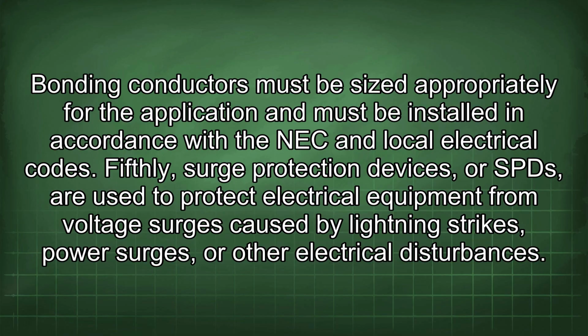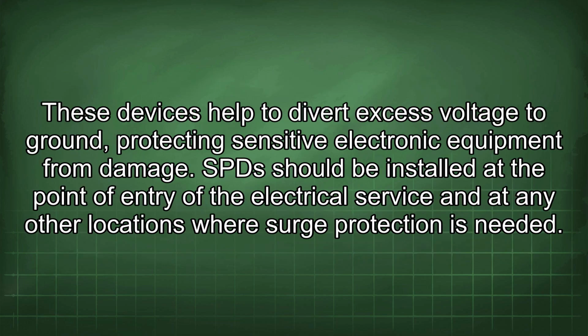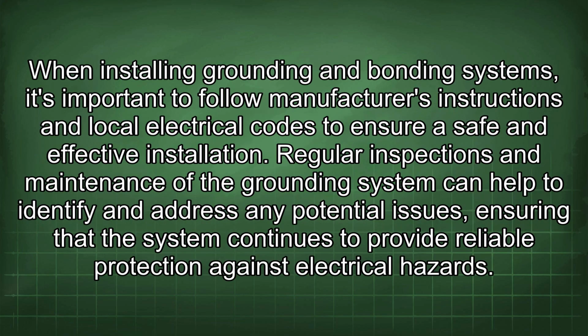electrical codes. Fifthly, surge protection devices, or SPDs, are used to protect electrical equipment from voltage surges caused by lightning strikes, power surges, or other electrical disturbances. These devices help to divert excess voltage to ground, protecting sensitive electronic equipment from damage. SPDs should be installed at the point of entry of the electrical service and at any other locations where surge protection is needed. When installing grounding and bonding systems, it's important to follow manufacturer's instructions and local electrical codes to ensure a safe and effective installation.